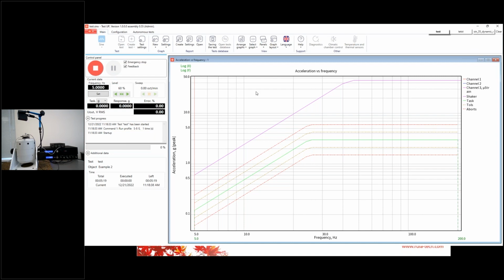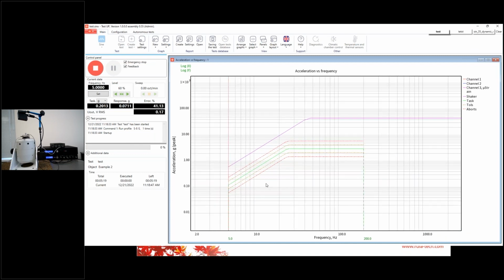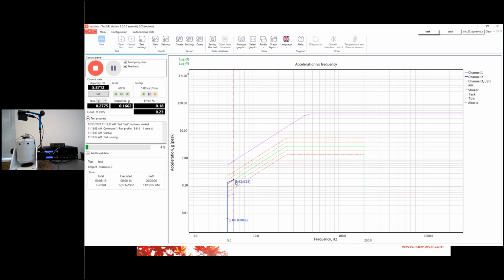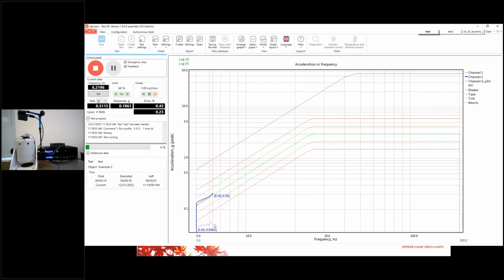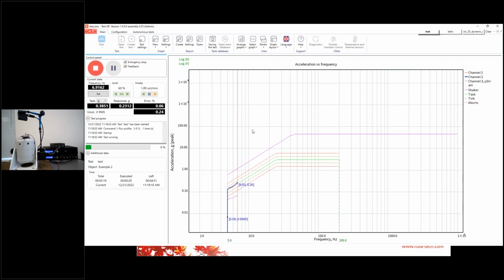On this acceleration graph, you'll see data from the strain gauge sensor, but it is shown not in G, in microstrain, so it can be a little bit lower than the main line. I think that you see that now we are moving. Let's select the second channel. It's our laser vibrometer. And here in the bottom, you see that we're measuring data from our strain gauge sensor. During this test, we'll get some resonances, and we need to check if our laser vibrometer and strain gauge sensor have the same frequencies. So I think it will be in the end of the profile about 200 Hertz or 160 Hertz.